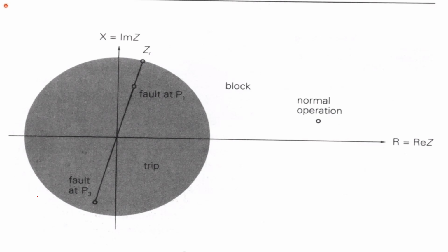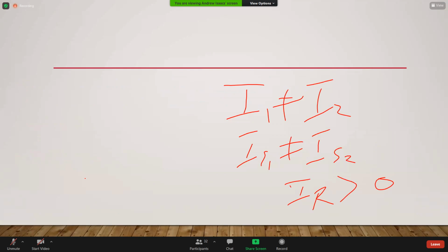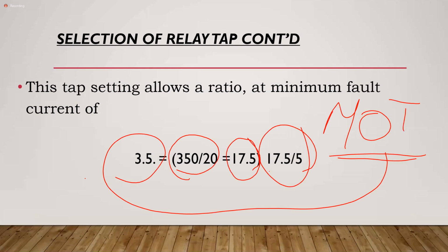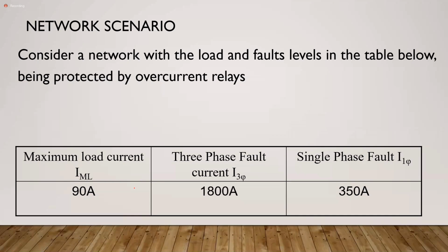Sir, question before you go, sir. Yeah, go ahead. In the scenario that we did earlier with our faults, was it a case that both the 1800 and the 350 were working from the primary? Yeah, that's what's on the system. Oh, so I was a bit confused. Okay, so this would be what's on the system. And remember what we said at the beginning, that once these currents exceed a certain value, we need the interface of a transducer. So that is what's on the system, and then the CT interfaces with the system and gives us an output. And then we treat with the output. In this case, we were looking at an overcurrent relay, but we'll also treat with that output whether we were looking at an impedance relay, et cetera. All right, sir. Thanks. You're most welcome.